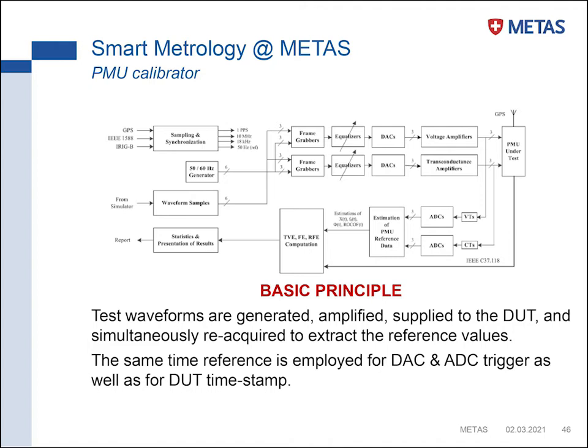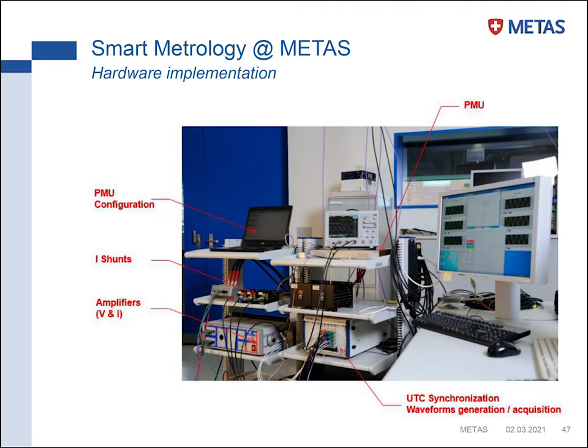And on the reacquired waveform, we extrapolate the reference values for synchrophasor, frequency, and ROCOF. And then when we know the reference values and we collect the PMU data packets, we can evaluate whether the errors are within the standard limits or not. As you can see, it's a quite complicated system, but this is one picture of the system in the lab, and it consists of an industrial controller like a National Instruments PXI, the amplifier for voltage and current, the transducers, our DUT, that is the PMU I showed you before, and the PC to control all the results.